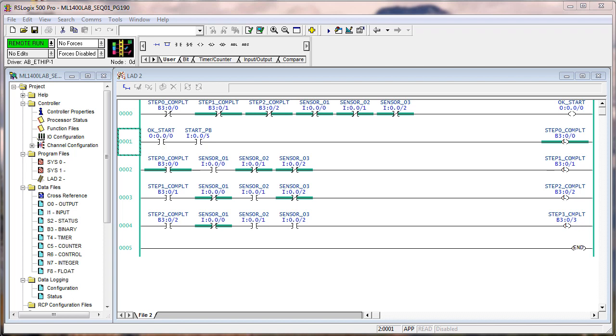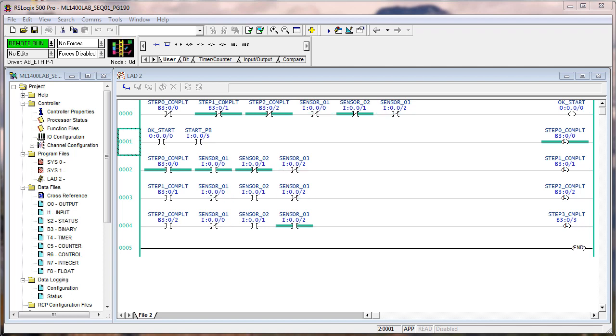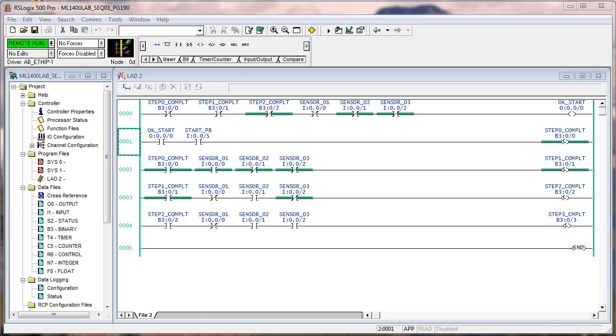Now with step zero complete, it's waiting for sensor one to be on, two and three to be off. So if I was monitoring a machine out there, sensor three could go on, and even though sensor one goes on, it still is not going to complete the next step until sensor three goes off. Then see it says step one complete, and now it's waiting for a new pattern for sensor one, two, and three.